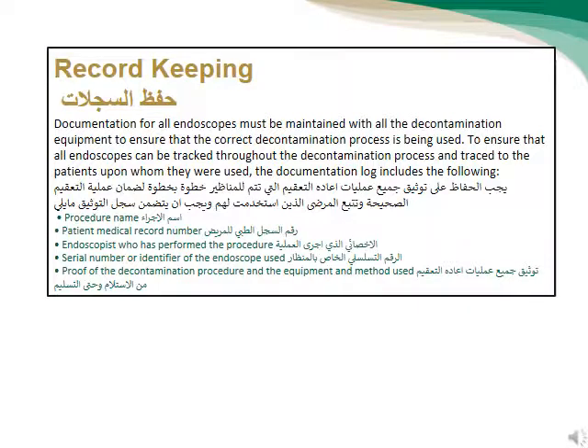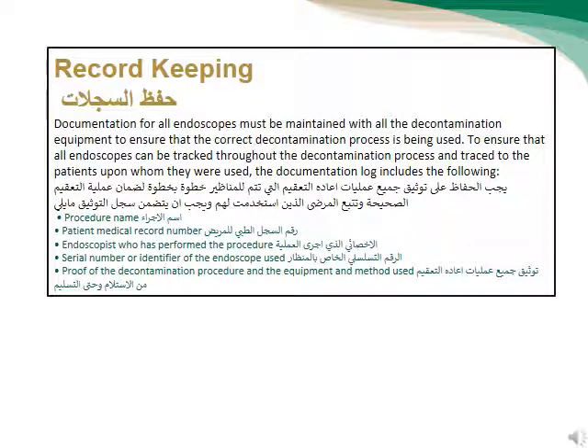Record Keeping. Documentation for all endoscopes must be maintained with all decontamination equipment to ensure that the correct decontamination process is being used. This also ensures that all endoscopes can be tracked throughout the decontamination process and traced to the patient on whom they were used.